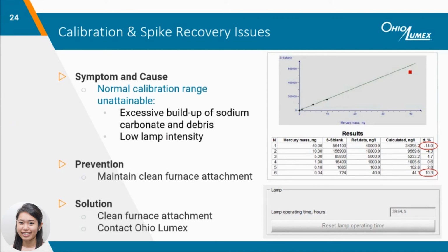If it becomes more difficult to pass your calibration according to the Method 30B QA/QC, it may be due for additional cleaning of the furnace attachment and housing. Check out pages 2 and 3 of the Guide to Troubleshooting and Preventative Maintenance or the M324 Maintenance Webinar for our recommended cleaning regimen. If the analyzer was just thoroughly cleaned and is still difficult to calibrate, the lamp intensity may be low and require a tune-up to improve the linearity. Contact Ohio Lumex for additional support if you suspect an issue with the optics.